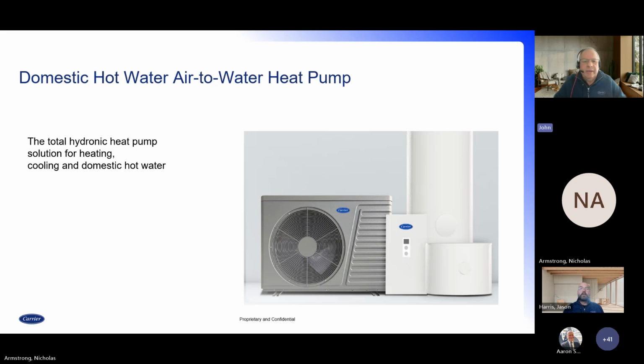A smaller tank down to the bottom right there is a buffer tank. It allows the outdoor unit to have proper running times, so it doesn't short cycle. At the same time, it provides a buffer of fluid, whether it be heating or cooling, so that if you're in a domestic hot water mode, it allows no interruption of either that heating or cooling. And just behind that is the domestic hot water tank. And as Nick was saying, this is a one-stop shop type solution for hydronic heating. It does your heating, it does your cooling, and does domestic hot water as well.